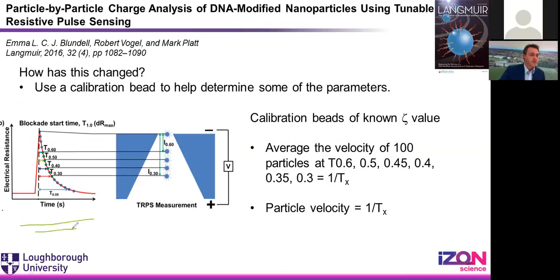I've got my diagram on the left-hand side here. I've got time versus resistance. This is my pulse that I've tried to draw. You have a pulse shape, and you're going to measure the width of the pulse at different points in time as you go across. Each one of these different time zones represents the particle moving through a pore. Instead of taking an individual measurement, where you might just measure the pulse at half height or a certain time frame, you would measure the pulse duration at all of these individual time points along the pulse, and you would take an average. You would take an average velocity of this, and it's 1 over this average that gives me my particle velocity.